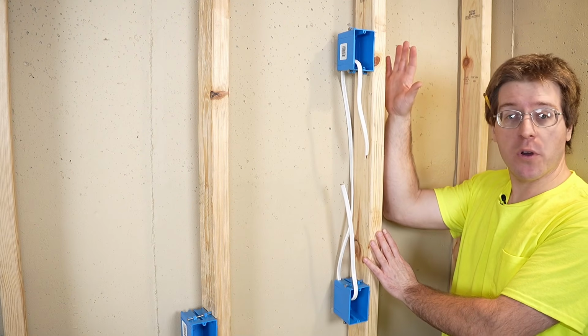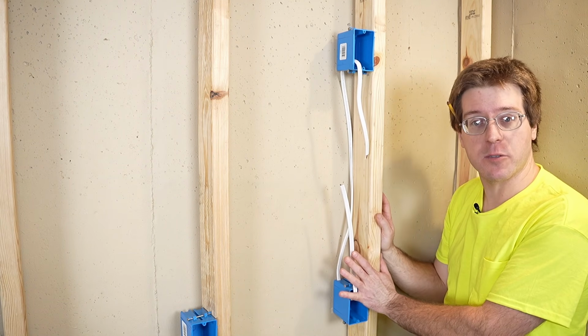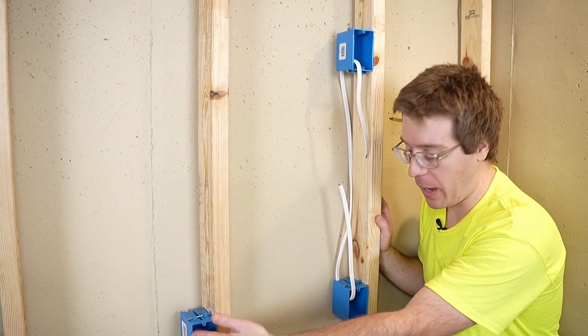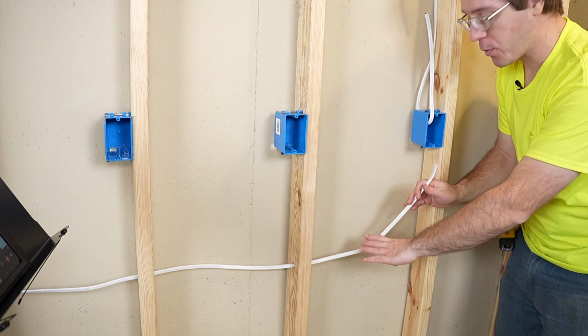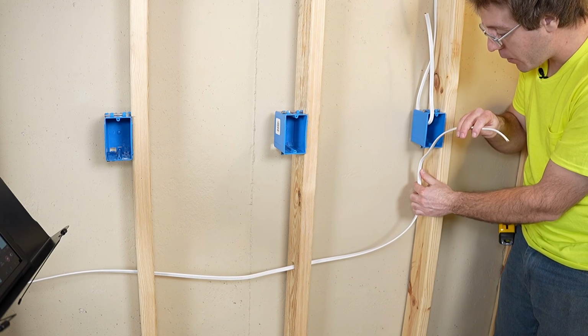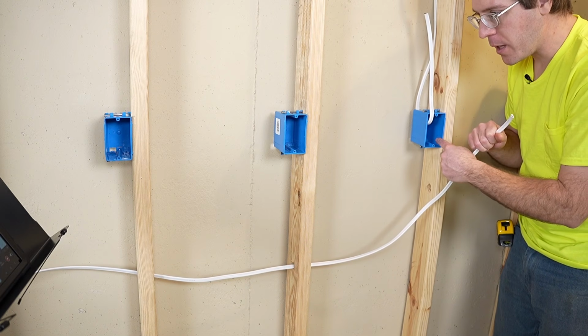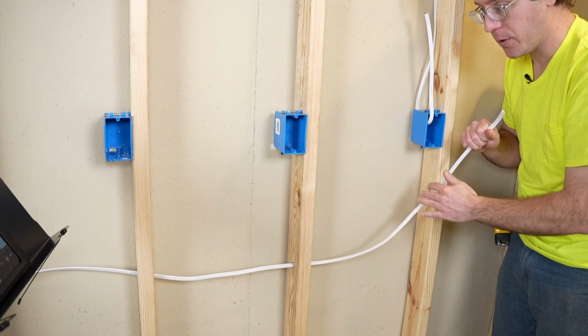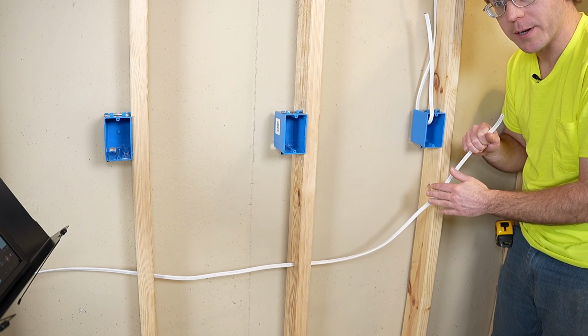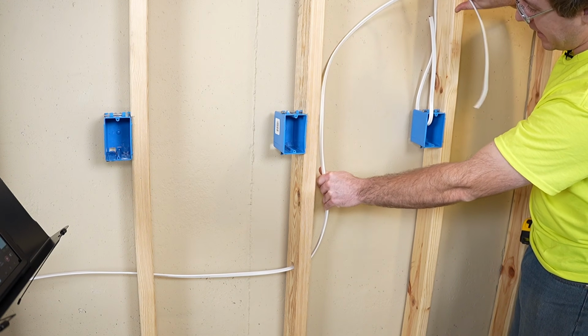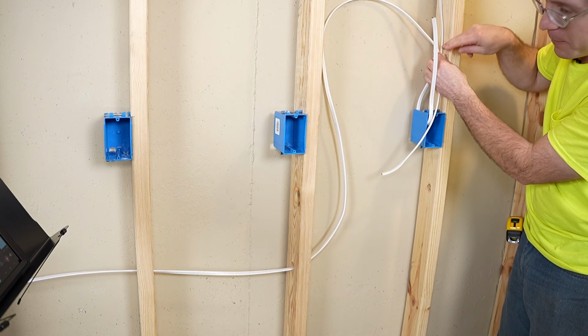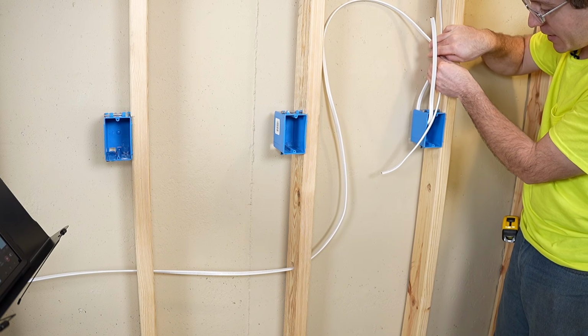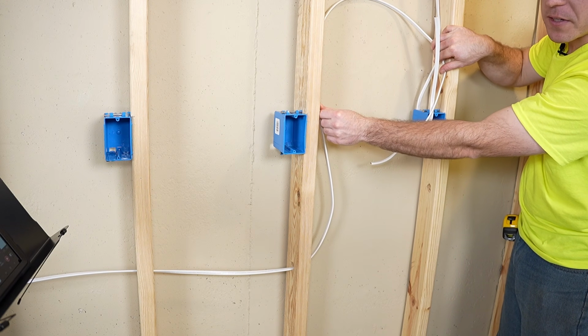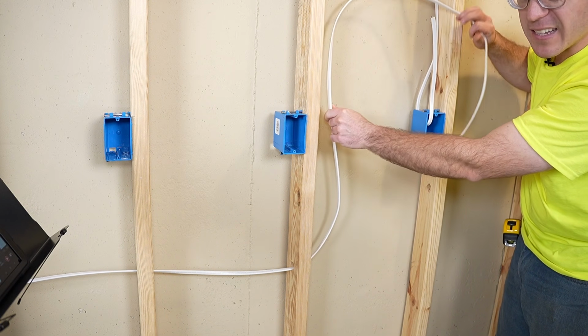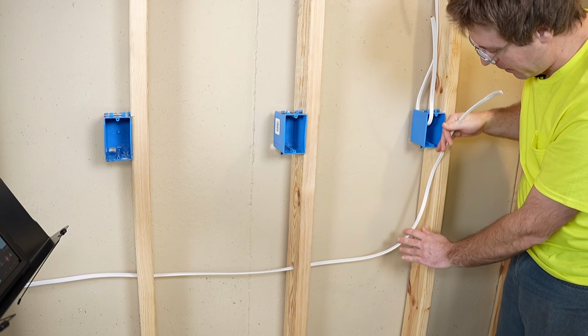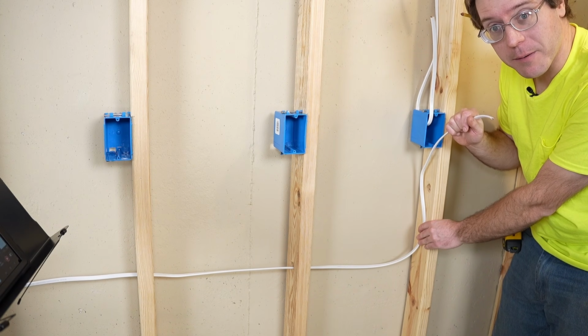Here's the big picture so far: we've got a wire from this box to this box, but now we need to loop to the previous box. So we take our wire coming through the studs and get another one up into this box. From here back, we'll have two cables entering the box—one input, one output. You could route it so one staple up top holds this set of wires together, with another staple over on this side—that's perfectly acceptable too, though it wastes some wire. So we're going to keep things short and come in the bottom of the box instead.